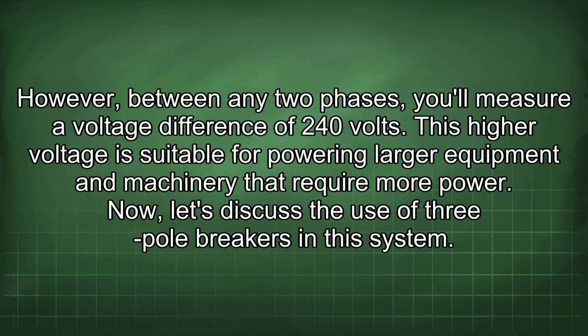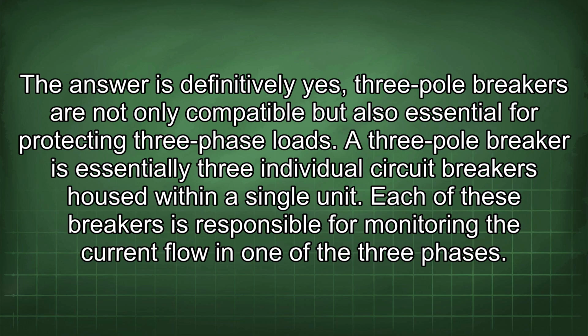Now let's discuss the use of 3-pole breakers in this system. The answer is definitively yes. 3-pole breakers are not only compatible but also essential for protecting 3-phase loads. A 3-pole breaker is essentially 3 individual circuit breakers housed within a single unit. Each of these breakers is responsible for monitoring the current flow in one of the 3 phases.